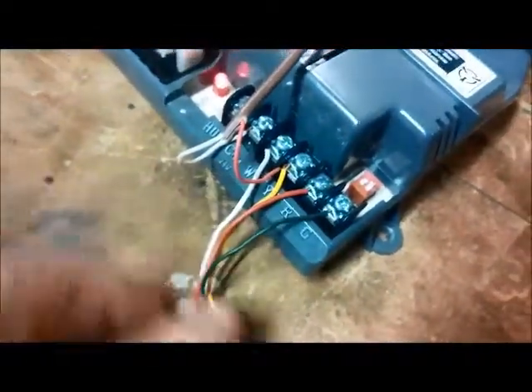So, say you turn on your thermostat and nothing's happening down here. The way you can check your thermostat is, basically a thermostat is 24 volt power fed off of R, which comes directly from the transformer, which is getting our 110 volts out of the board, feeds it back into the board. And if the transformer's good and we have 110 volts, that's going to transform 24 volts to this R terminal here. So that R gets sent up to the thermostat through the thermostat wire and it ends up right here at our R. And you're going to need these four wires.